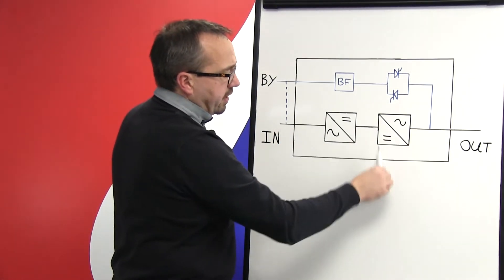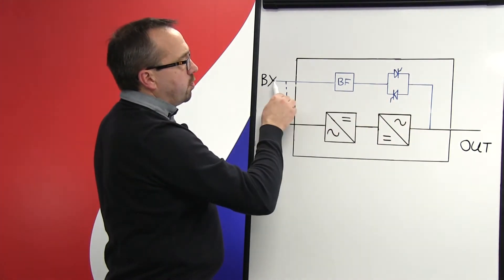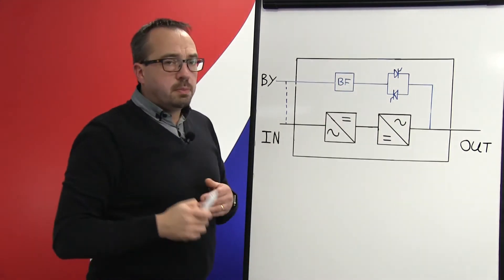If there's no main supply and the UPS is supplying the connected load from the batteries, we don't want any power trying to flow back through the static bypass switch, and therefore the back feed protection device prevents this.